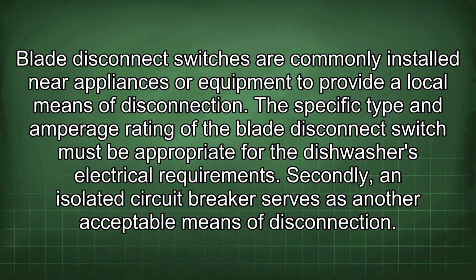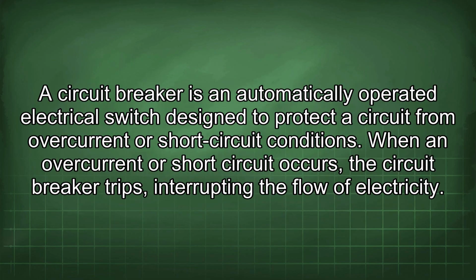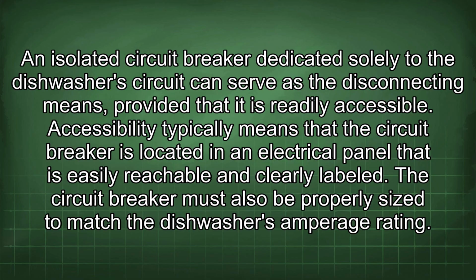Secondly, an isolated circuit breaker serves as another acceptable means of disconnection. A circuit breaker is an automatically operated electrical switch designed to protect a circuit from overcurrent or short circuit conditions. When an overcurrent or short circuit occurs, the circuit breaker trips, interrupting the flow of electricity. An isolated circuit breaker dedicated solely to the dishwasher's circuit can serve as the disconnecting means, provided that it is readily accessible. Accessibility typically means that the circuit breaker is located in an electrical panel that is easily reachable and clearly labeled. The circuit breaker must also be properly sized to match the dishwasher's amperage rating.